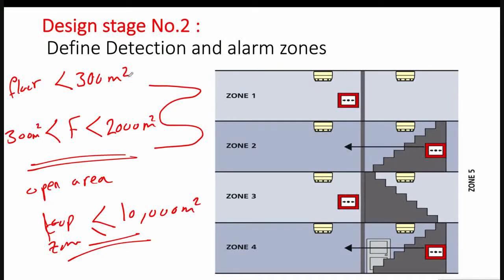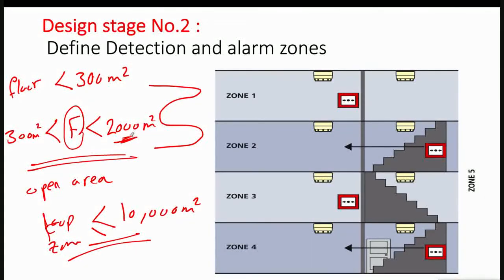Unless the floor area is less than 300 square meters, if the floor area is between 300 and 2,000 square meters, you should assign all the floor to one loop. You can also assign it to more than one loop, because the area may include many rooms requiring a large number of smoke or heat detectors — more than a single loop can support.